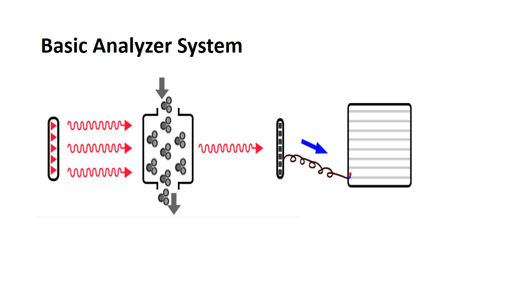The detector outputs a signal that is proportional to the amount of infrared waves falling on it. So more CO2 in the sample chamber causes more infrared to be absorbed and less reaches the detector. Less CO2 in the sample chamber causes less infrared to be absorbed and more reaches the detector. So if the patient has low CO2, more infrared reaches the detector, low CO2 display. High CO2, less infrared reaching the detector, high CO2 display.